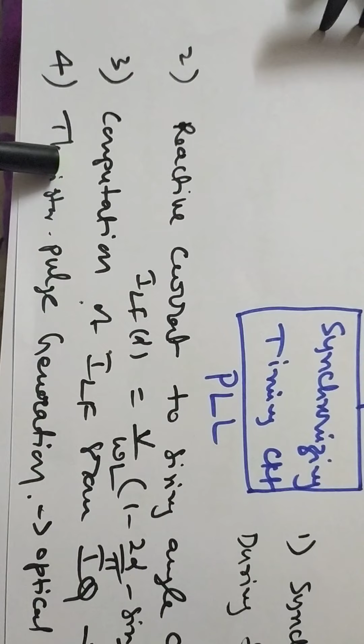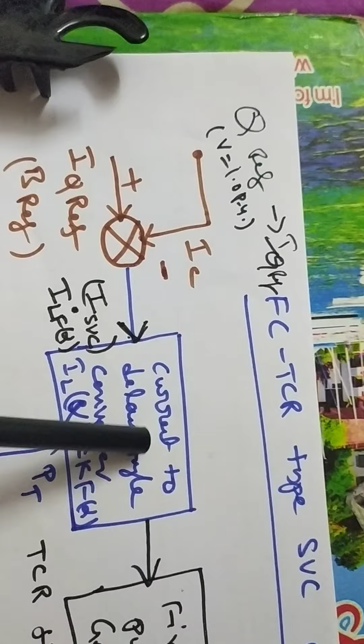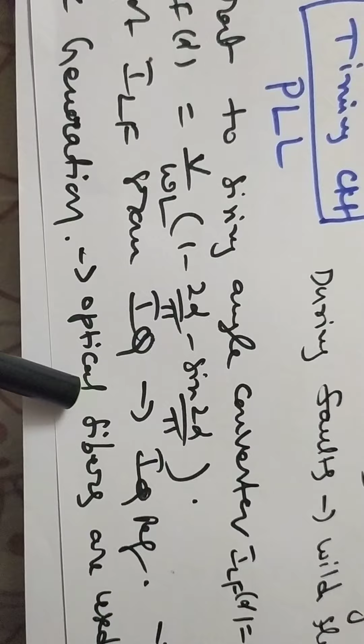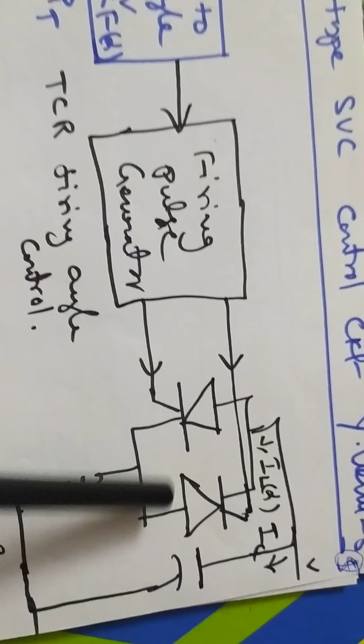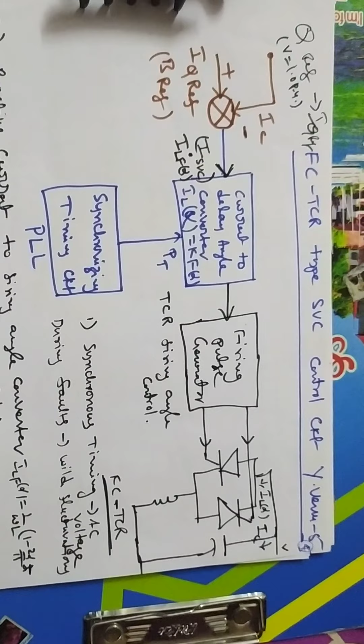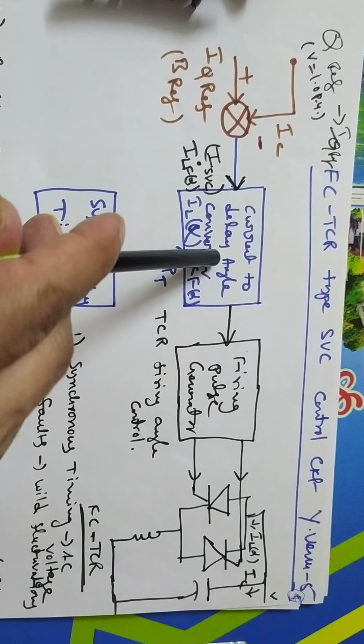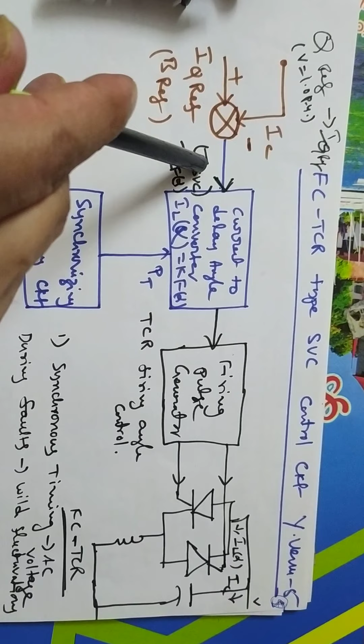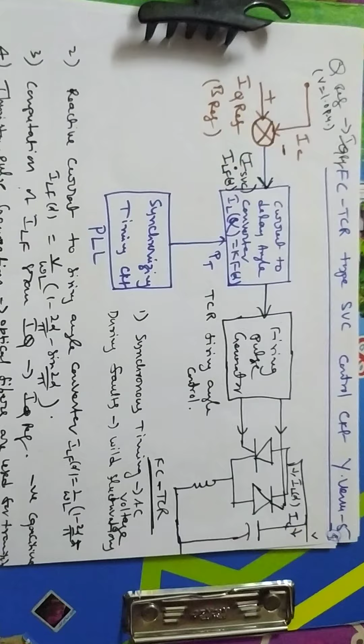The third function is finding the ILF alpha value from the IQ reference value from the comparator. So this is the comparator. This is the third function. The last one, the fourth function, is generating the thyristor firing pulses and firing the TCRs through optocouplers and optical fibers. So in summary, the first function is to generate the synchronizing timing signals in synchronism with the system voltage. The second function is obtaining alpha from the known ILF. Third, from the IQ reference, obtain the ILF alpha. And fourth, generate the firing pulses appropriately to the anti-parallel thyristors. So this is the control of your FC-TCR type SVC of the system.